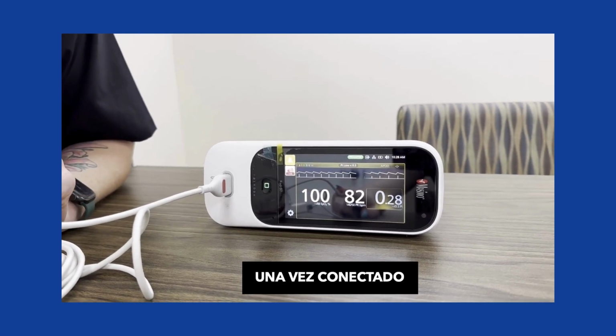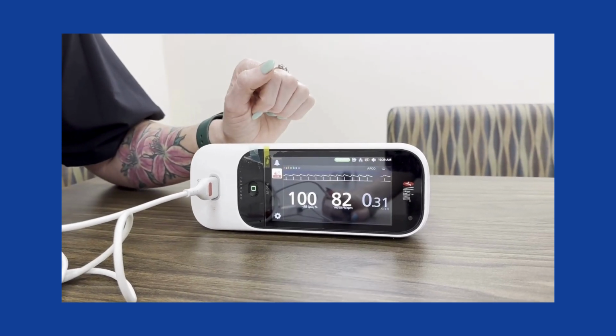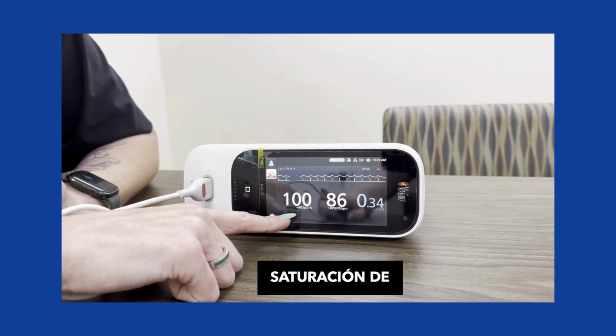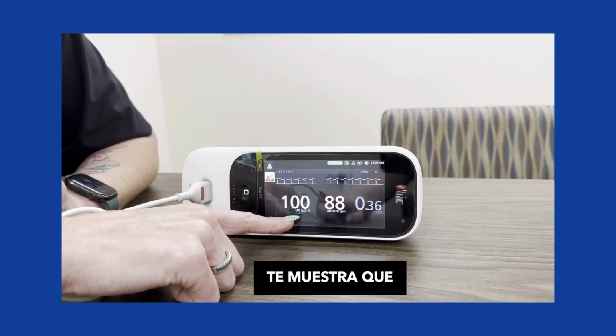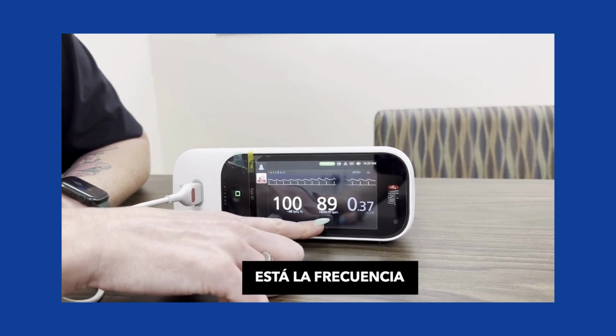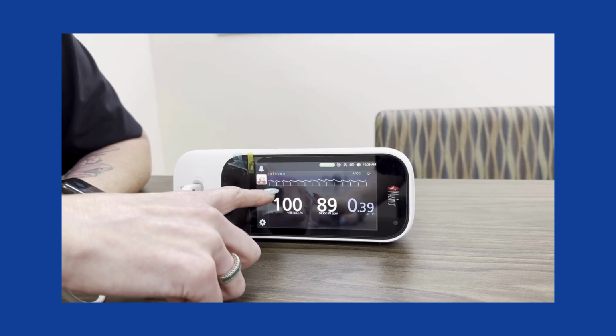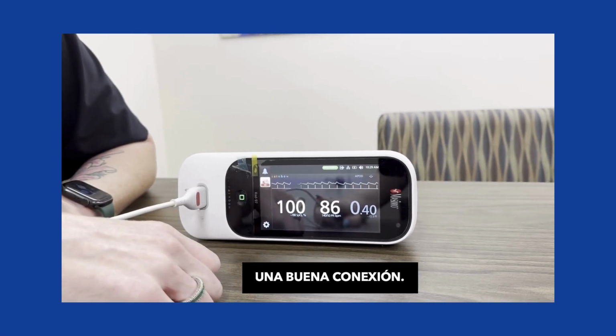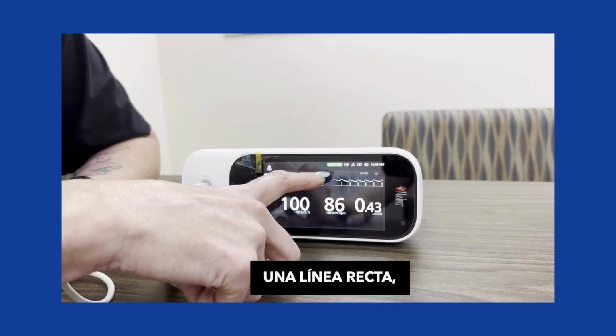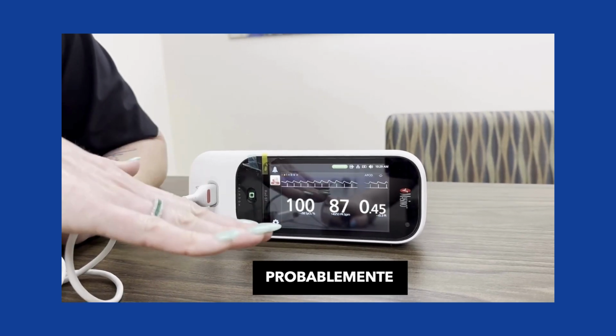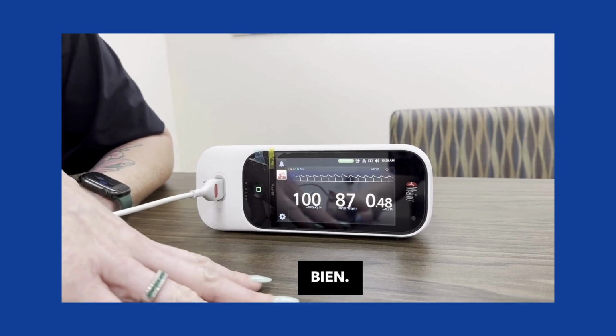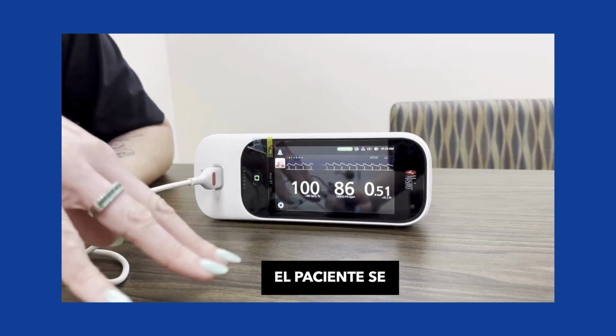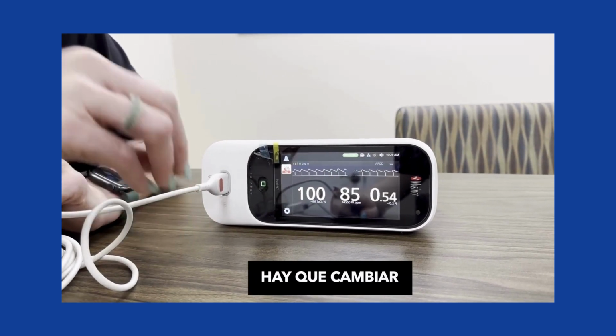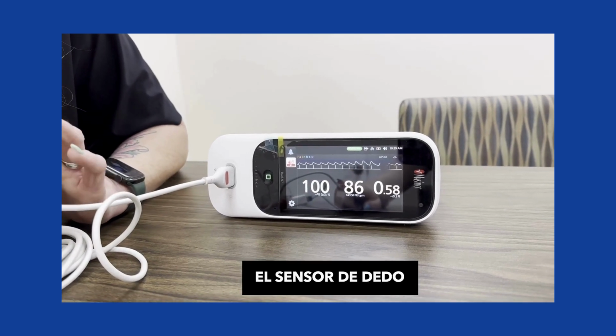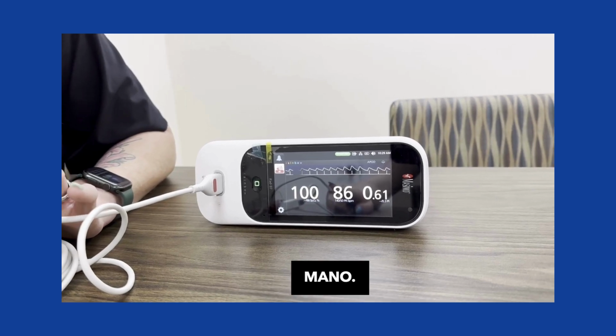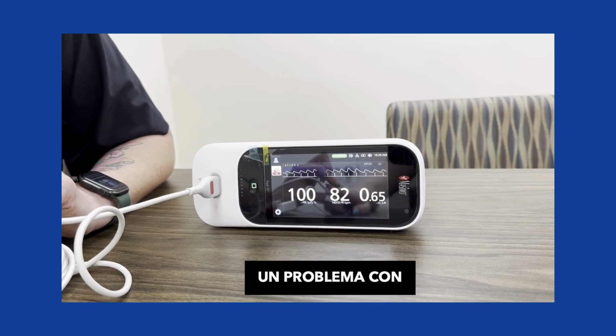So once you have your pulse ox hooked up properly on your patient, the first number you're going to see displayed is the oxygen saturation. So it's showing you that it's at 100%. And then here, of course, is what the patient's heart rate is. You should also see a corresponding waveform to tell you that it's a good connection. So if you notice that this waveform that's going across the screen starts to be a straight line, it means that it's probably not picking up very well. It also means that maybe the patient is moving. So sometimes you just have to literally move the probe from one finger to another, or maybe sometimes the patient's hand needs to be warmed up, but it's just usually that there's something wrong with the probe.